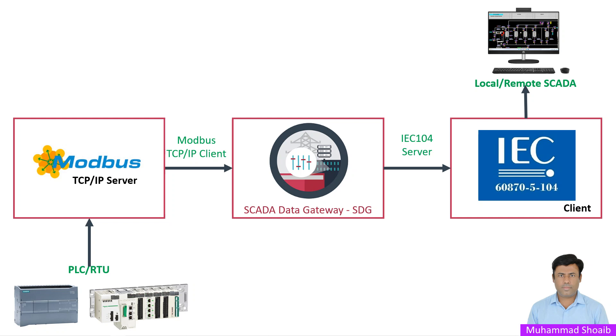My name is Muhammad Shoaib and today in this tutorial video we will learn how we can convert Modbus TCP protocol into IEC 104 protocol. IEC 104 protocol is very common in water network industry and power industry. Sometimes you have devices that you want to integrate with the command center like a remote SCADA, and those devices only support Modbus TCP or Modbus RTU protocol. You can use SCADA Data Gateway (SDG) to convert Modbus TCP protocol into IEC 104 protocol.